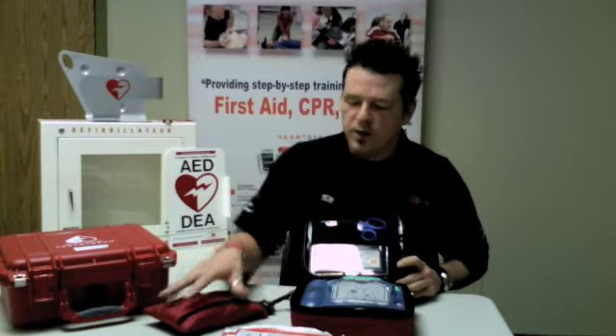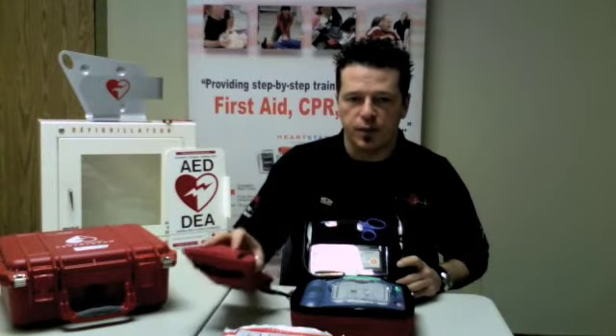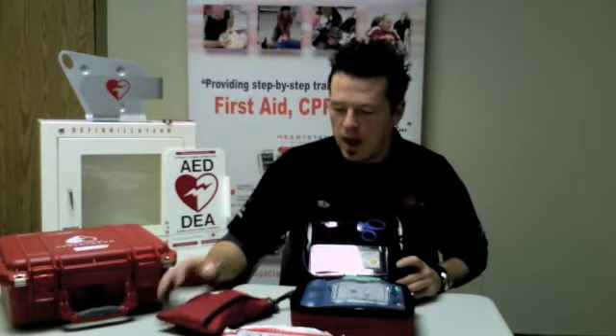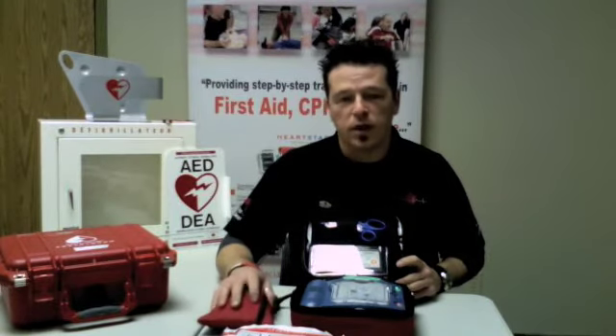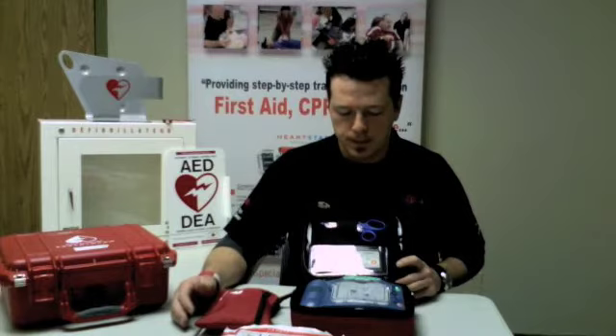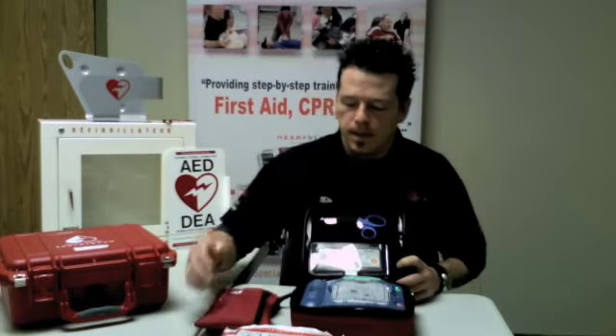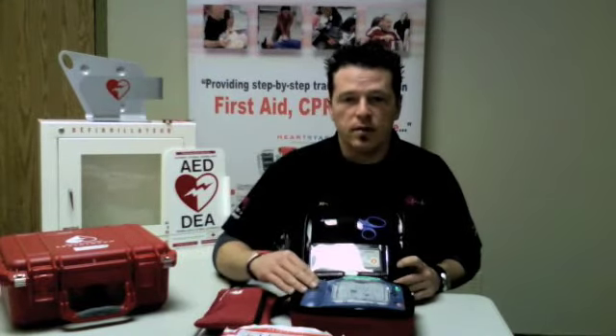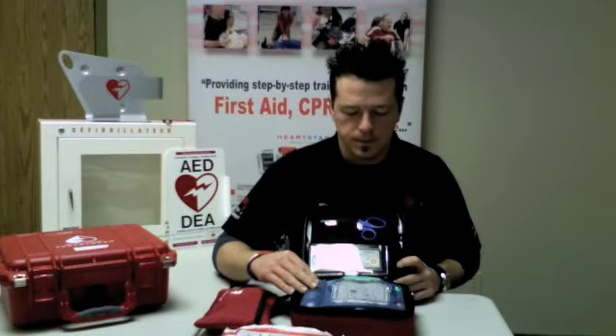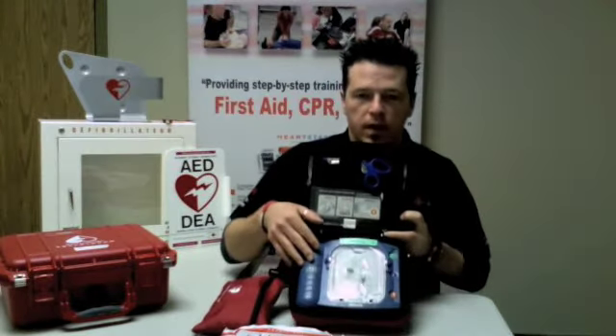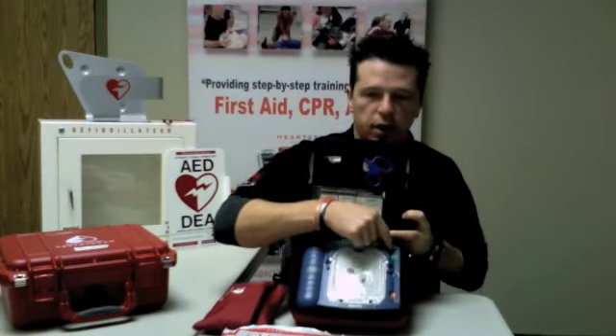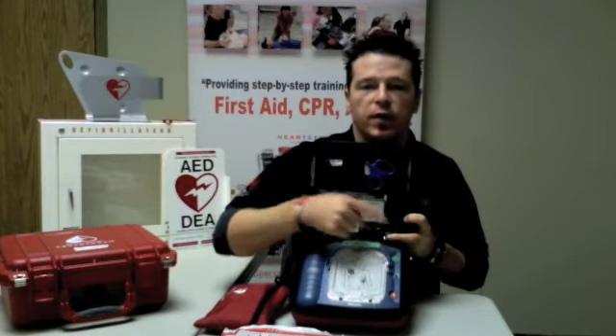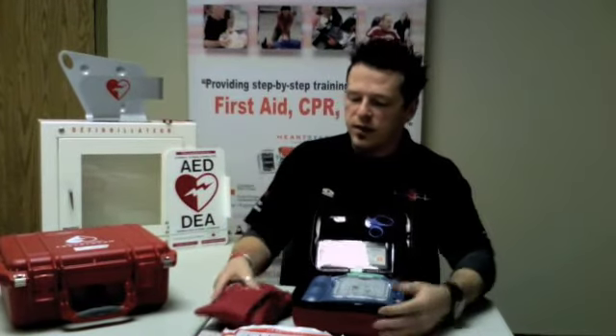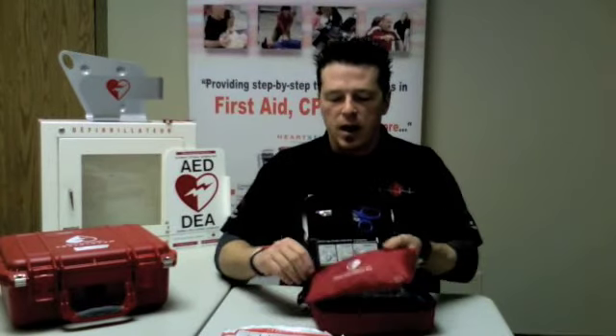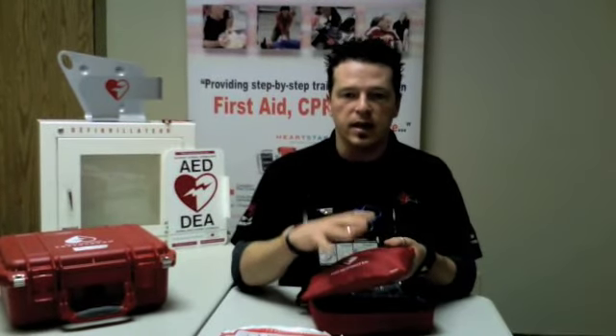Testing. There is a fast response kit that's attached to the defibrillator. And there are 5 things within this fast response kit. As you may have heard there was a clicking sound. Ready for use. In case of emergency, press the green on-off button. And as you will see, that little green light has now shut off and will now start to flicker every 4 to 5 seconds. Now, as mentioned in this fast response kit, there are 5 things that need to be maintained in a little kit attached to the defibrillator.